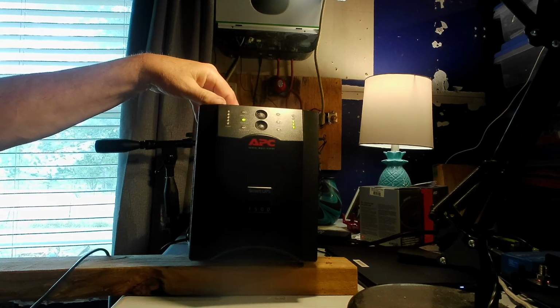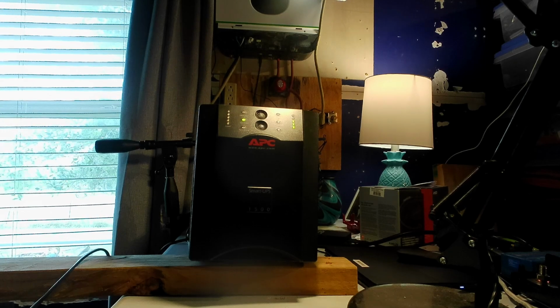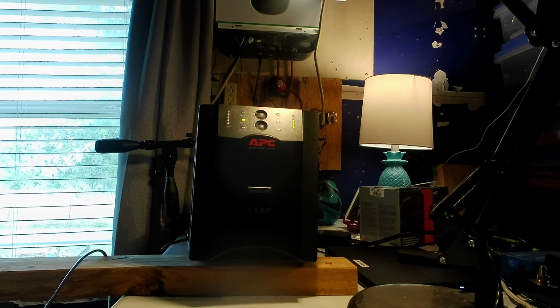Anytime you change out a battery on a UPS, you need to hook your load up to it, your full load, and do what's called a runtime calibration. What that'll do is it'll try to exhaust the battery till it gets down to 5 or 10%. I don't recall exactly what the exact number is. And then it'll determine how long it could run with the load on the current battery that you have when it's fully charged. So that can be a long process.